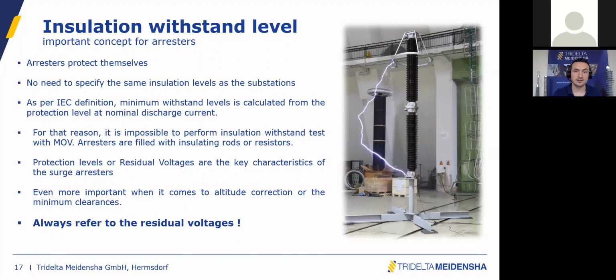So just a summary here. As I said, the arresters protect themselves. So it's the responsibility of the manufacturer to tell you what the minimum insulation level for the arrester housing is. And basically, the utility should not worry about that as long as the protection level is properly dimensioned and the protective distances are respected. The best example I can give is that when we go to the test lab to do the insulation withstand level test according to IEC, you never do the test with the MOV inside. Otherwise, it will never flash over, because the MOV will protect the arrester.